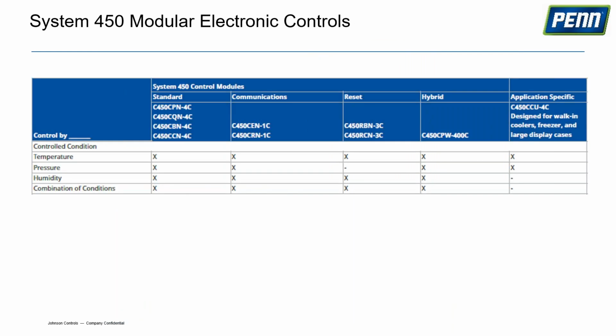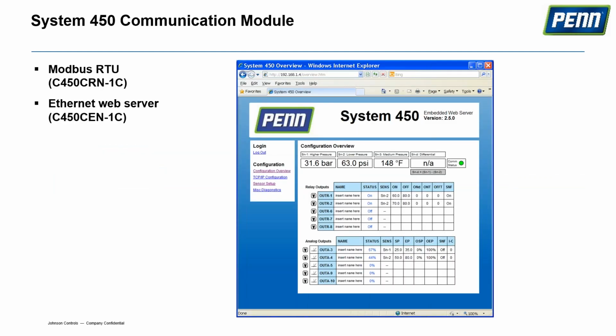Here's a kind of a summary of what I just went over. What I want to point out is that there are two communication modules, the CEN-1 and the CRN-1. These two modules are either Modbus, the CRN, or Ethernet, and here is what the website looks like. So you can actually change settings and you can monitor the actual sensor values through the website. This does not have cloud-based connectivity, but it does allow you to remotely connect to the device by using the communication modules.